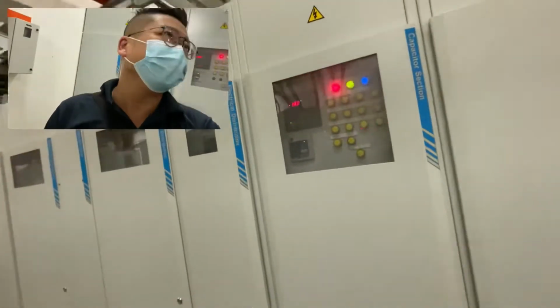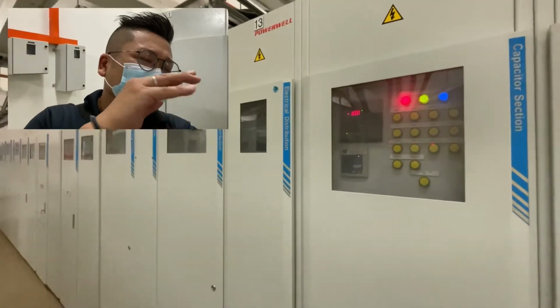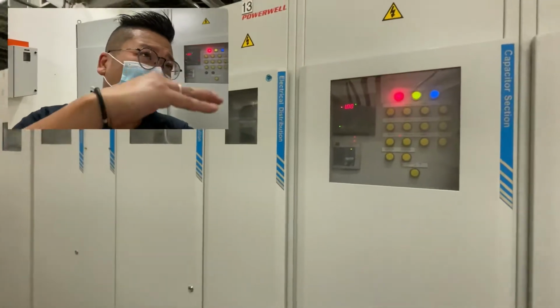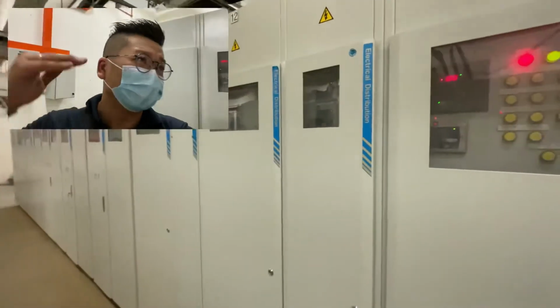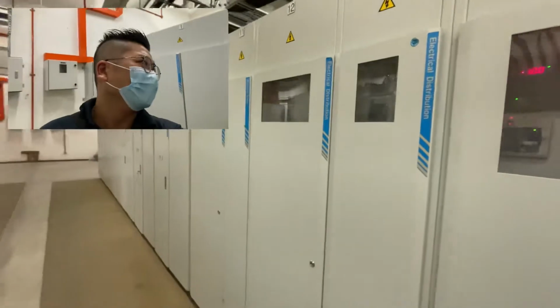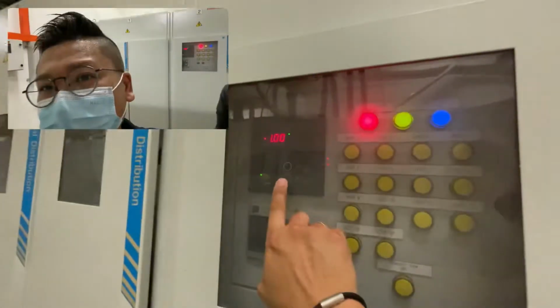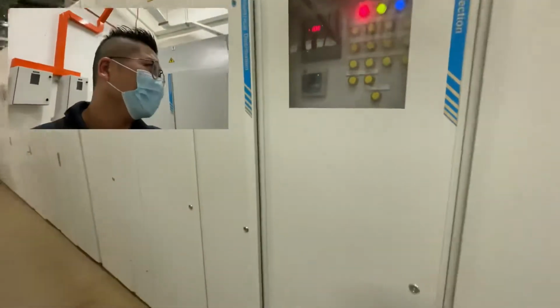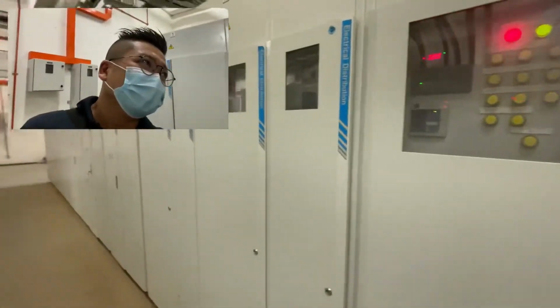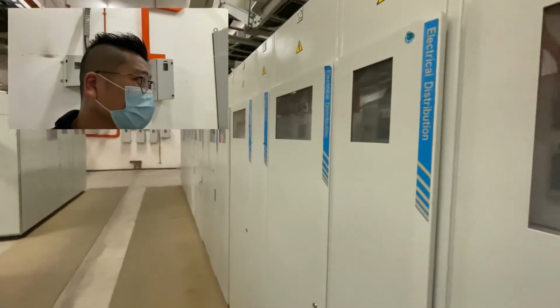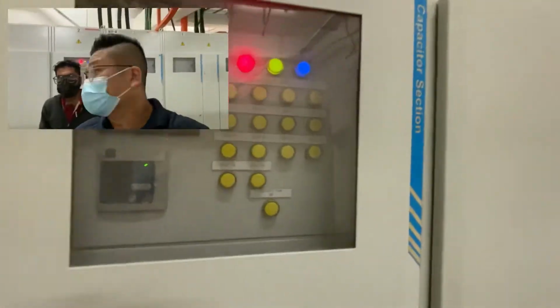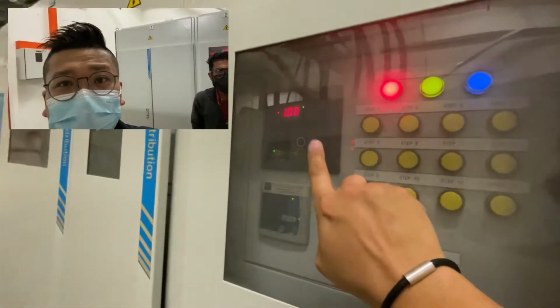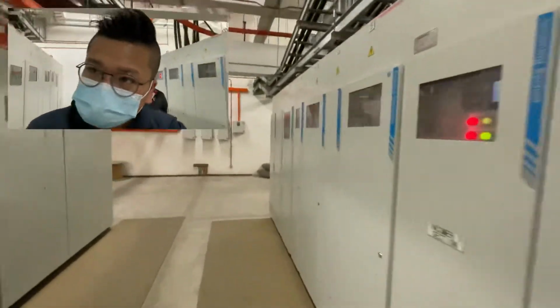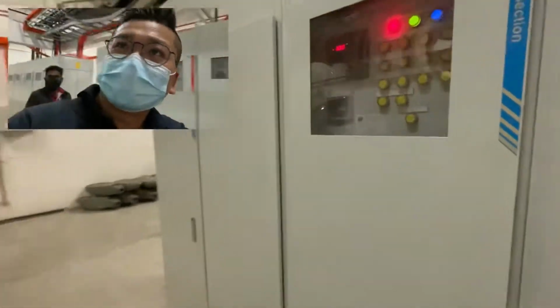Oh. 240. If let's say at normal rate like now, if it goes like 250, then it's on the high side. You need to adjust your transformer tap. Oh, okay. So you need to do calibration, am I right? During servicing time, adjust the transformer tap using tap 1 or 2 to lower down the voltage ratio. Okay, this one is a power factor. Currently it's at unity, no problem. Okay, on the MSB 1 also at 1, no problem.